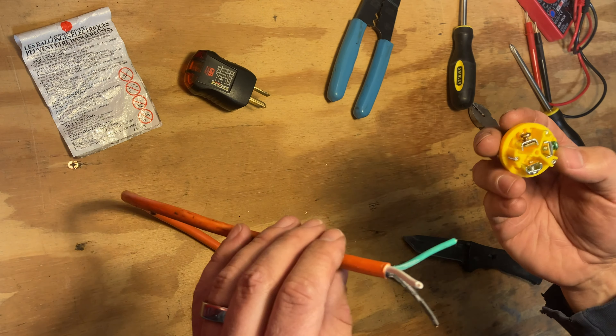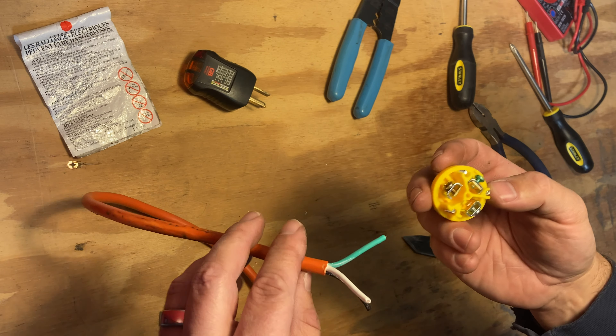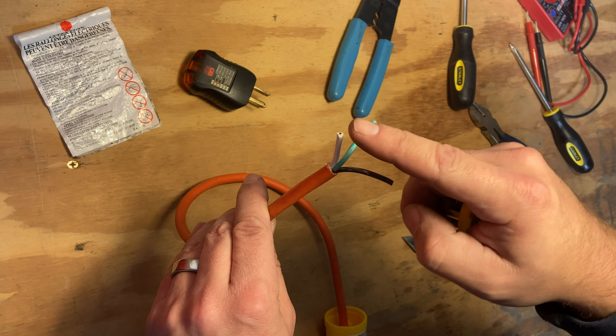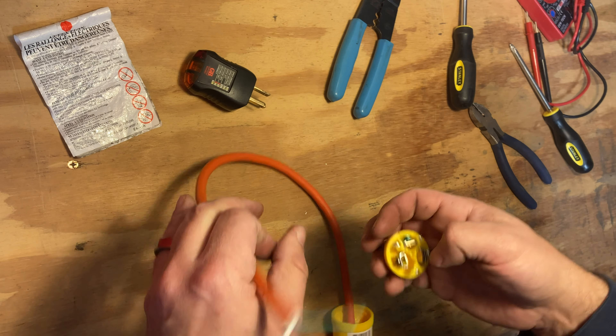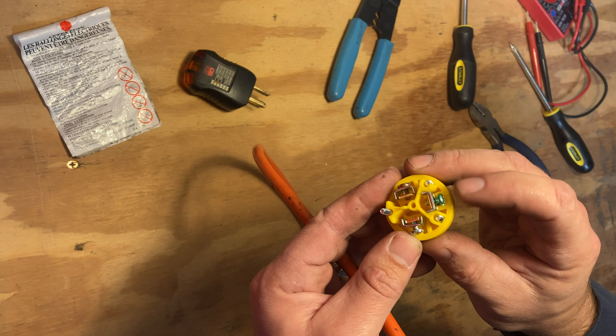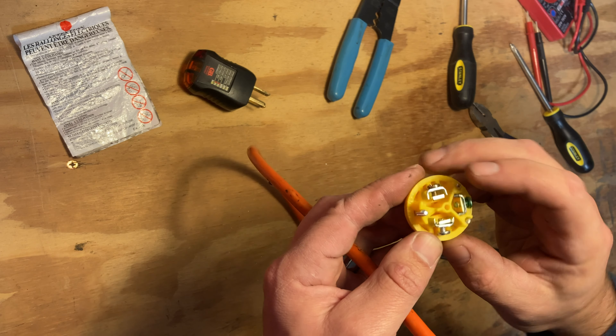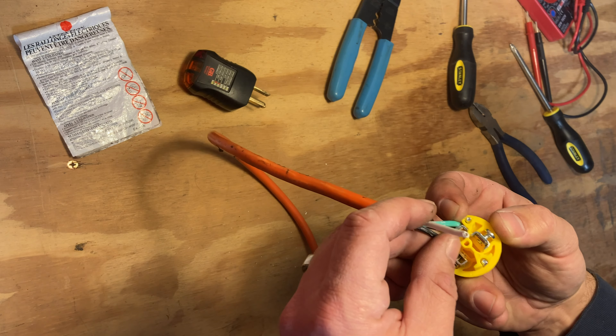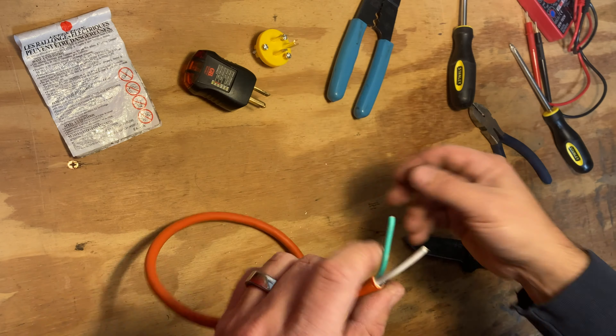Now, you can't just wire this any old way — that's a great way to start a fire or worse. You'll notice this cable has a green wire, a black wire, and a white wire. And in this plug you have three different screws: a green-tinted screw, a silver screw, and a brass screw — or as I like to think of it, a green screw, a light screw, and a dark screw. I always connect green wire to green screw — that's universal. Then black wire to the dark screw, and white wire to the light screw. That's how I remember it.